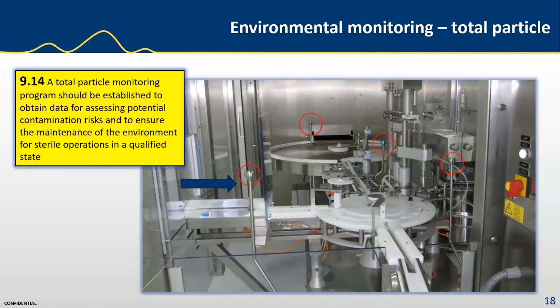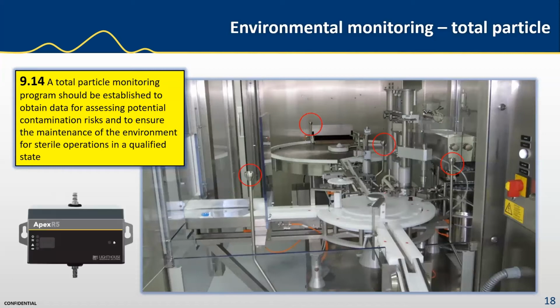So remote particle counters are used for this type of monitoring. In this image, the samples are taken via isokinetic sampling, and the sample probes, which are made from stainless steel, are connected to the inlet of the remote particle counter. We've got an example of a remote particle counter here.